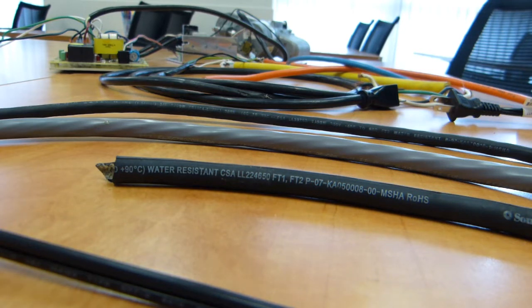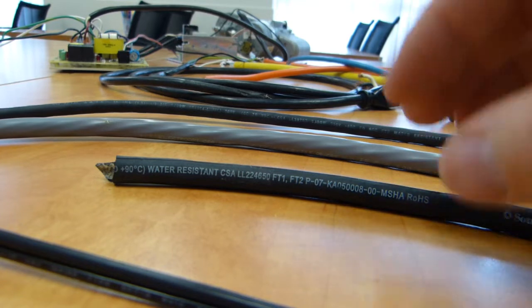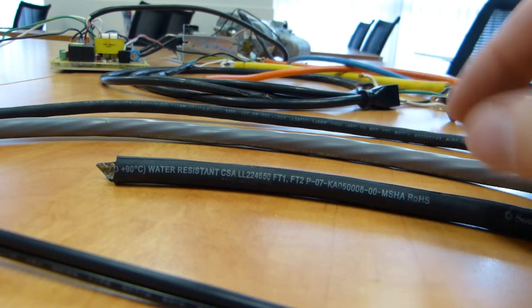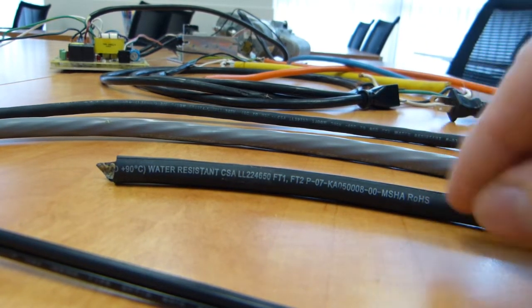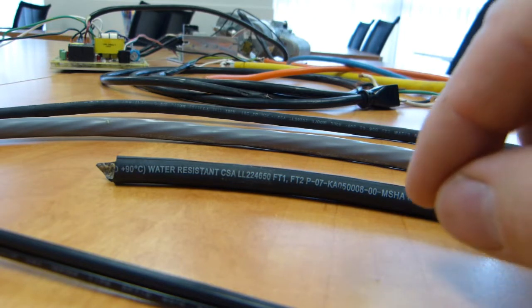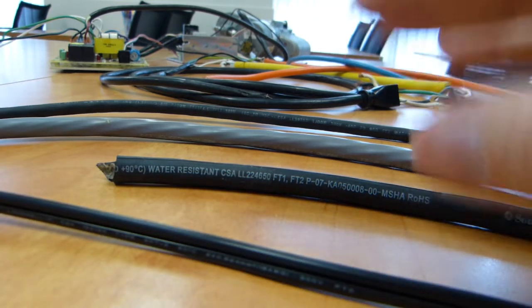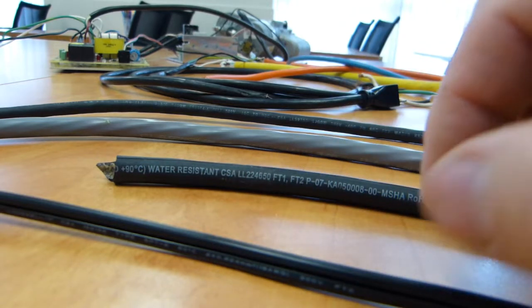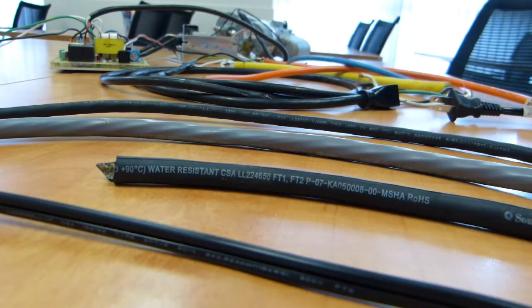So that's what these numbers mean - they are maximum amounts, considering both the air temperature around the cable and the hot surface on which the cable is laid. I hope that makes sense. You're not supposed to exceed this temperature rating given the service conditions.